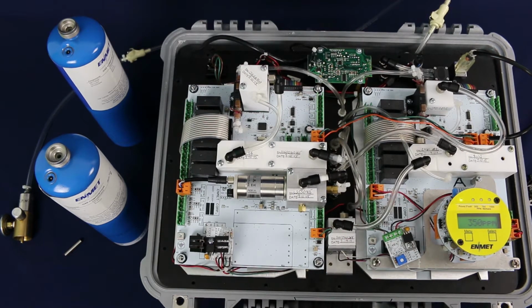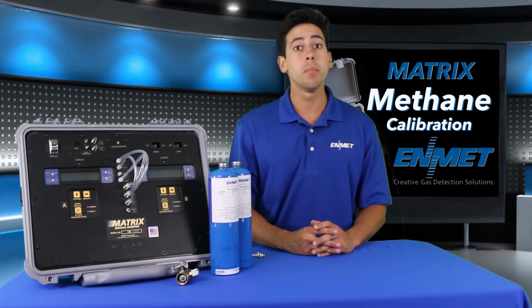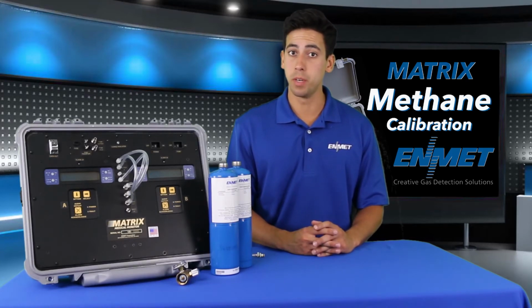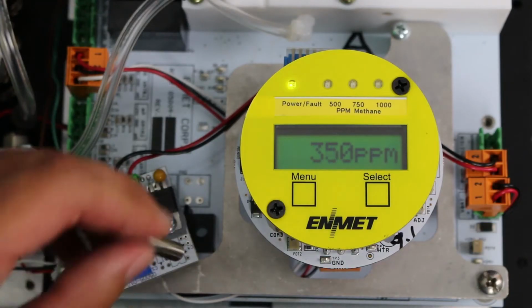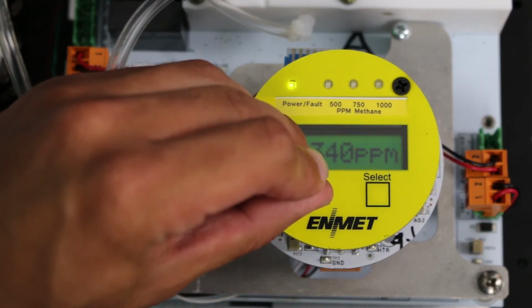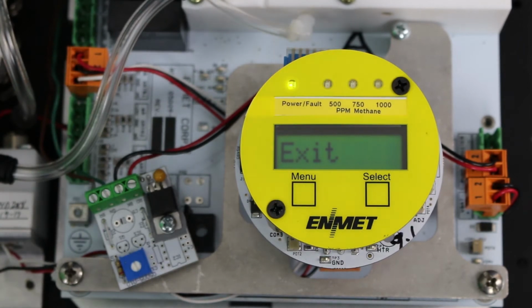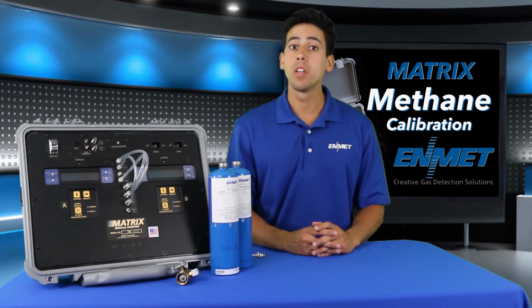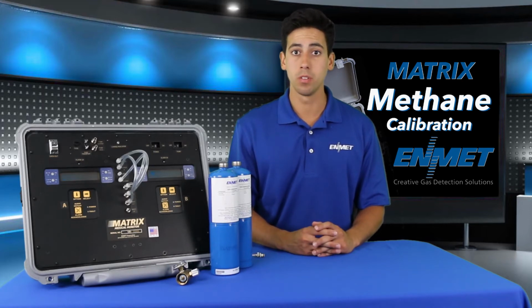The first step to starting your calibration is to enter the maintenance menu on the sensor transmitter by pressing and holding your magnet on the menu key for 3 to 5 seconds until you see the word exit appear on the display. At this point, you are now in the maintenance menu. The zero function must be performed by exposing the transmitter to clean air using your zero gas cylinder or clean compressed air. The zero procedure steps are as follows.